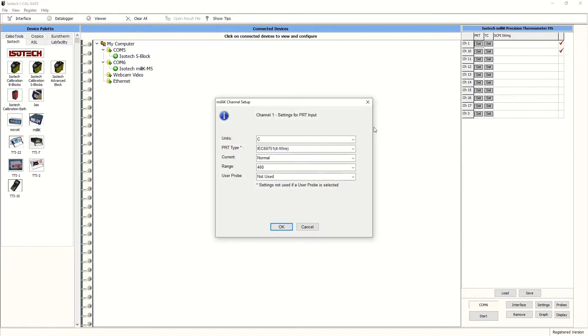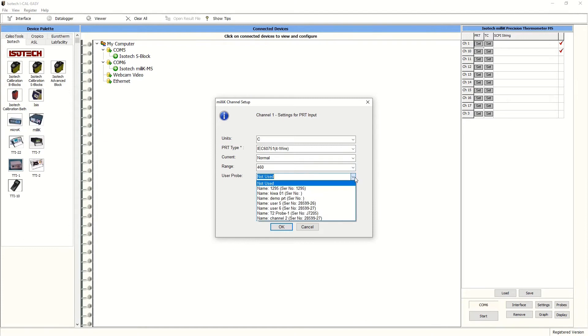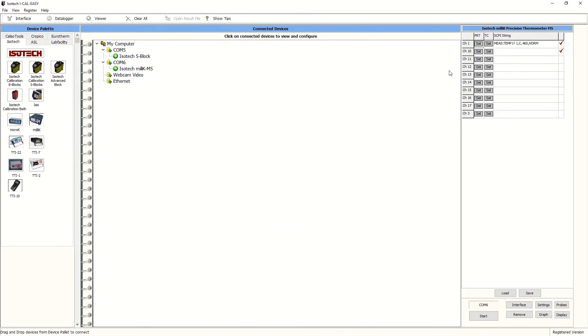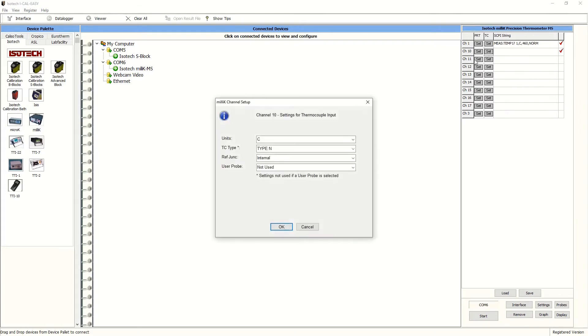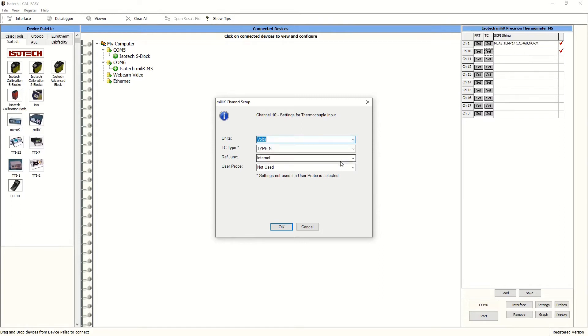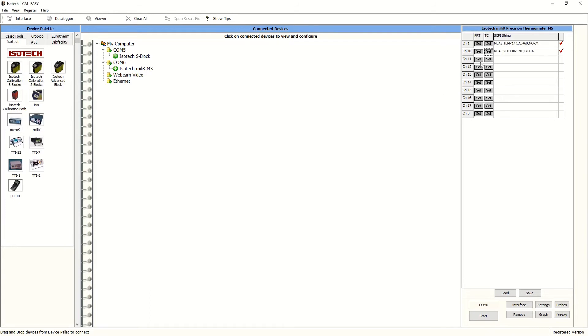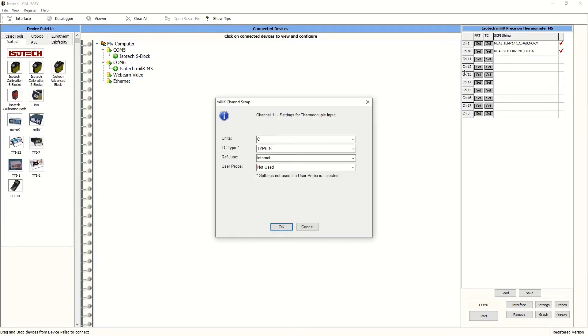So channel one is a PRT on the milliK itself and we mentioned that this would be our reference. We're going to read in degrees C. This is already logged in the milliK itself as a user probe. Then we'll label each of the other positions, such as the thermocouples. We can change the outputs of the signal from degrees C to millivolts and repeat the method for each of the positions accordingly.